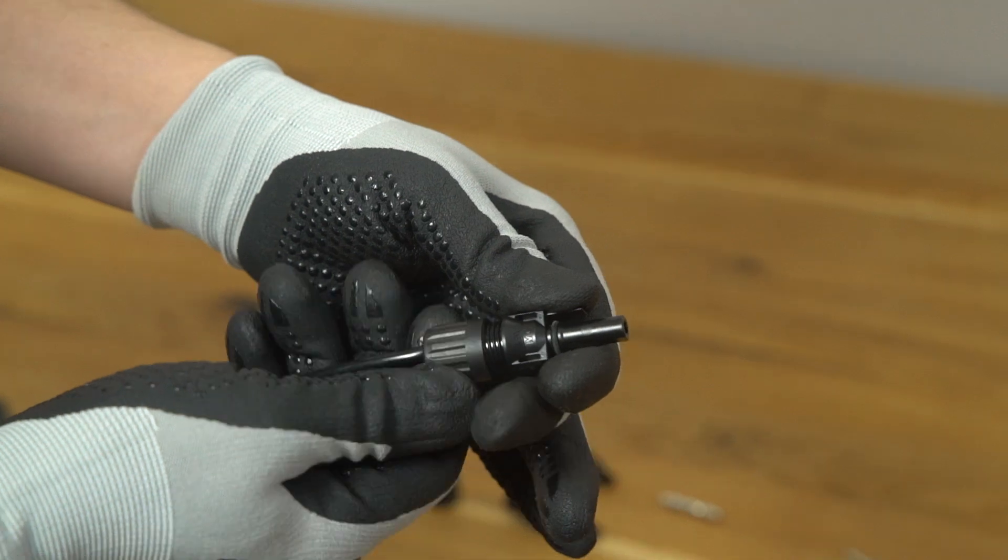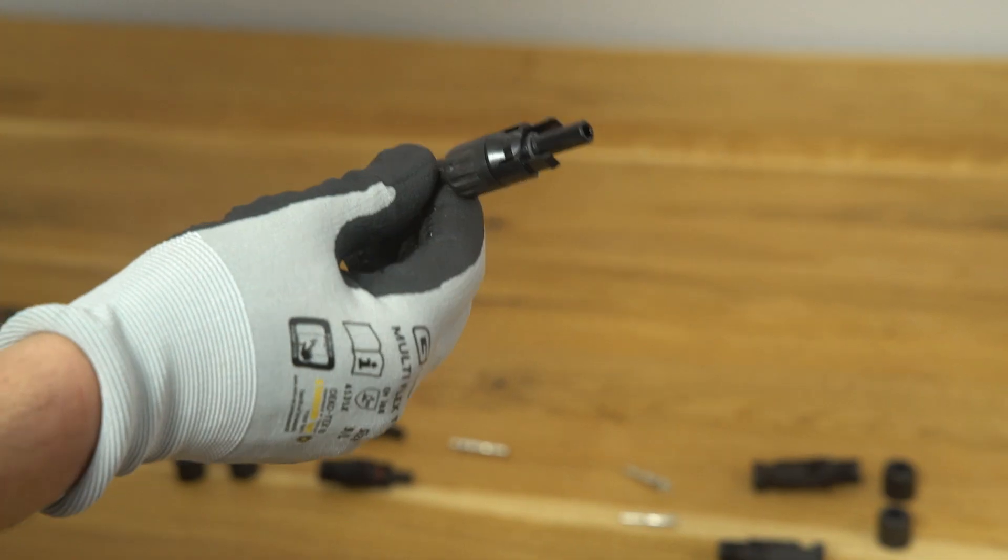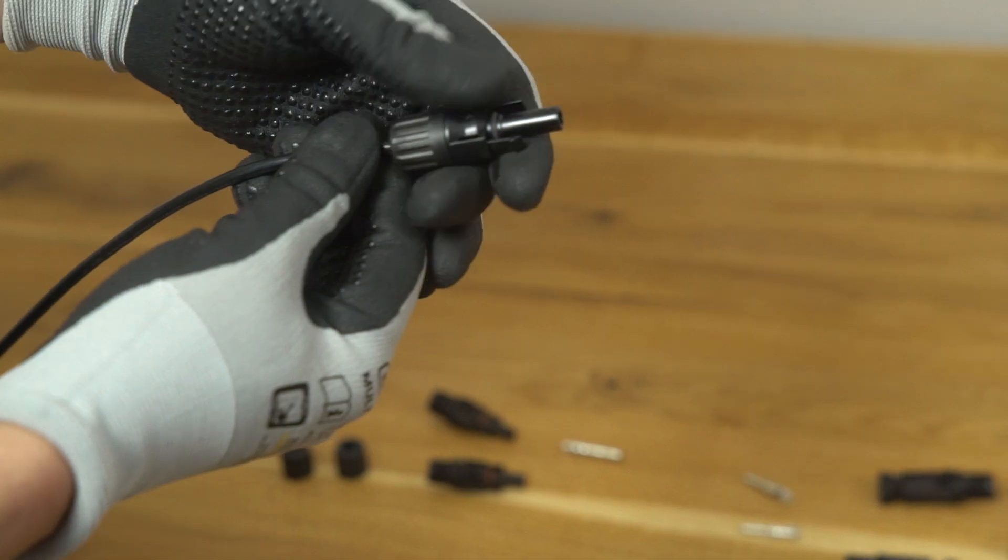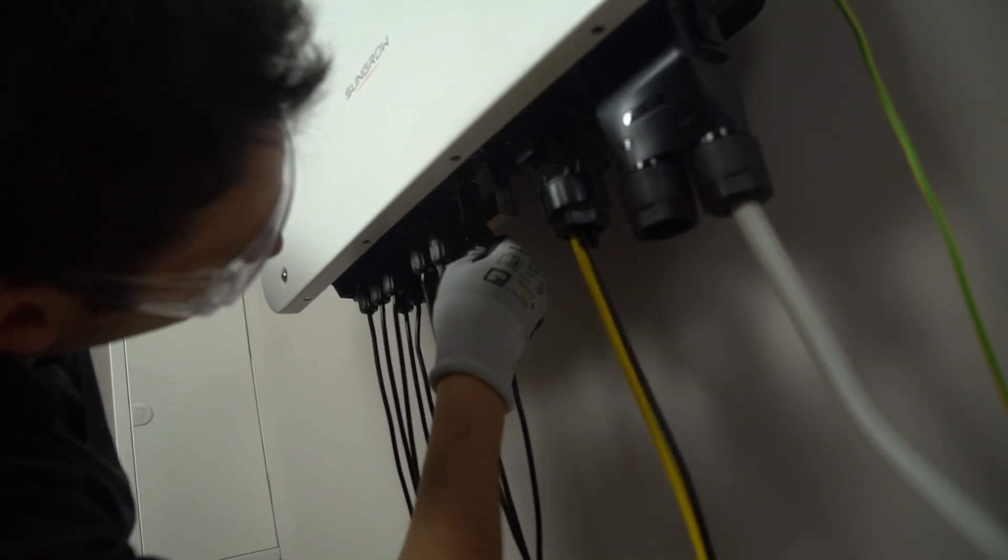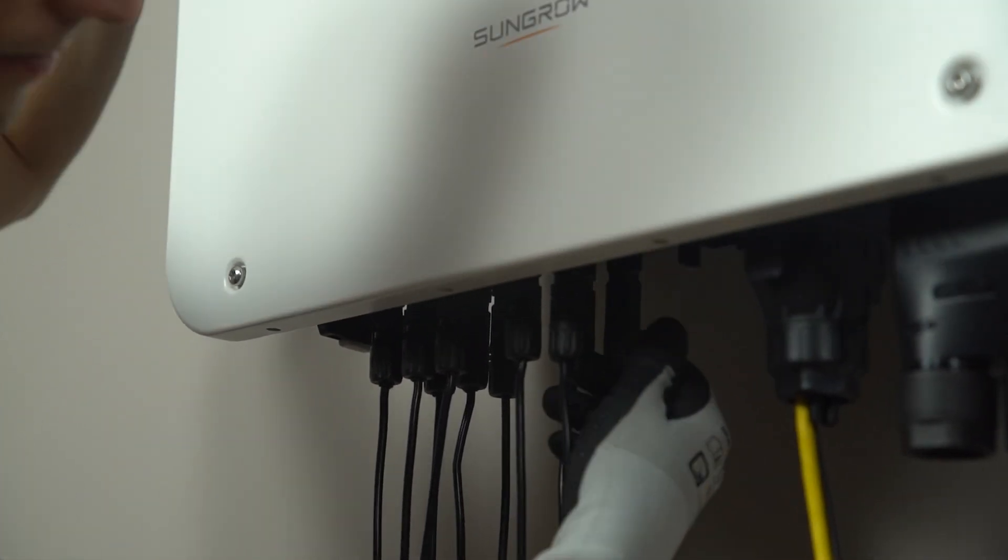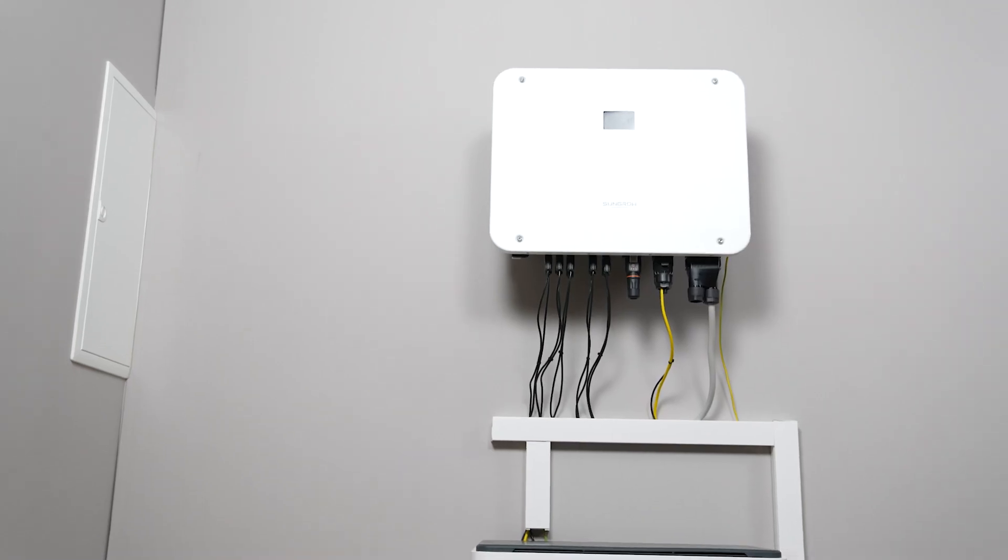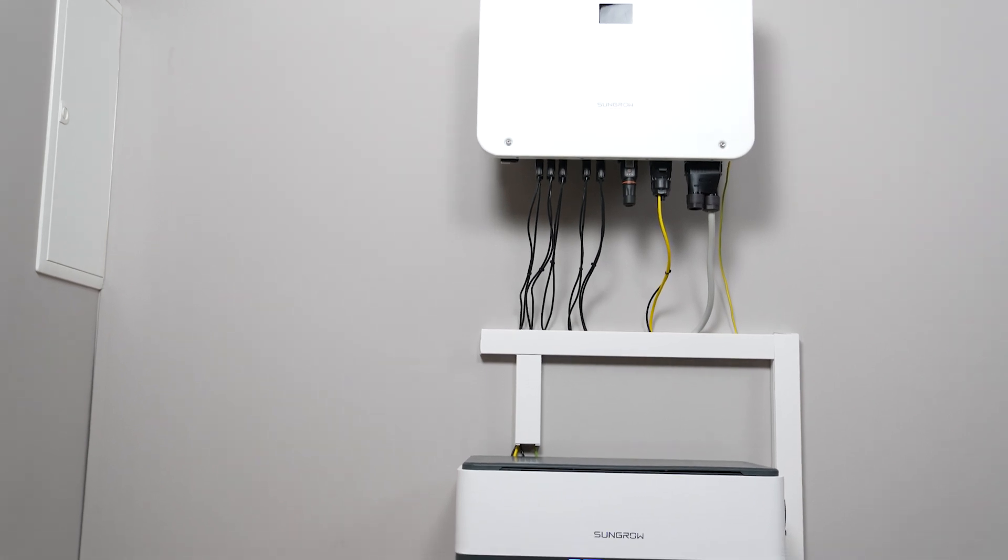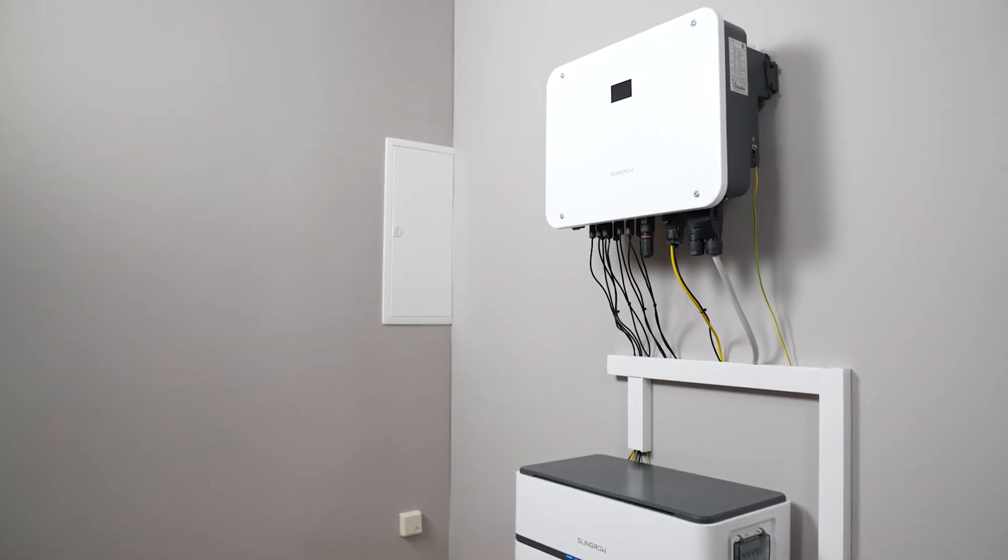Tighten the cable gland with the MC4 wrench. Check again for polarity correctness and plug the connectors into the BAT plus and BAT minus terminals. A clear click can be heard. The cable connections on the inverter side are done for the battery connection. Check out SunGrow's SBH installation video to continue the installation on the battery side.